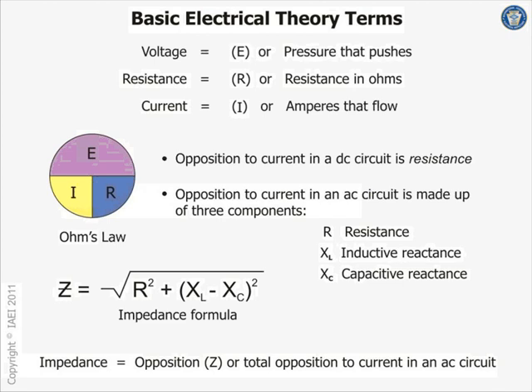I don't know if it bothers you guys. What the heck is capacitive reactance in a conduit that's carrying three conductors and a neutral at 277? You have 3 circuits, right? 3 circuits, 20 amp each. A 277 lighting circuit, 3 circuits, 3 hot phases, phase A, phase B, phase C, and a neutral, a multi-wire branch circuit in an EMT conduit. Now it has an inductive reactance.